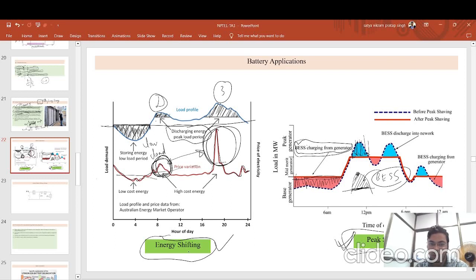This energy shifting and peak saving concept is there. Energy shifting means you should charge the battery during off-peak hours and low load time frames, and discharge this power during peak hours. Peak shaving means reducing this extra peak demand down to a certain level by discharging the extra power. So these are two important concepts: energy shifting and peak saving.